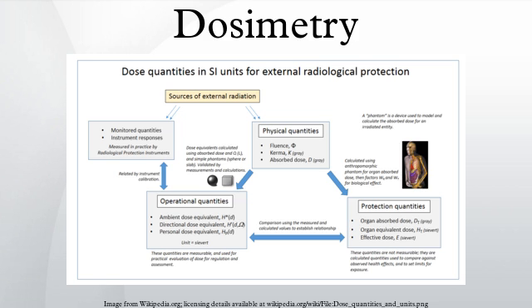These are worn as badges, but can give an indication of instantaneous dose rate and an audible and visual alarm if a dose rate or a total integrated dose is exceeded. A good deal of information can be made immediately available to the wearer of the recorded dose and current dose rate via a local display. They can be used as the main standalone dosimeter, or as a supplement to such as a TLD badge. These devices are particularly useful for real-time monitoring of dose where a high dose rate is expected which will time limit the wearer's exposure.